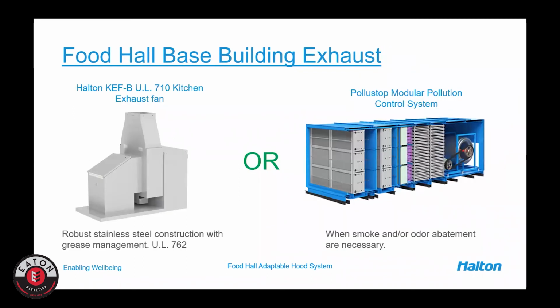In terms of the base building design, we would work pretty early on with the design team in determining what are the real requirements of the project. If we need perhaps a pollution control unit, if there are adjacent spaces, or this is perhaps in a commercial, residential, or a mixed development use, we would certainly look to a pollution control unit for designing a system that's going to do a good job of capturing grease, smoke, and odor, so we don't have any nuisance odors for nearby tenants. Or if not, we could look to a standard upblast exhaust fan.